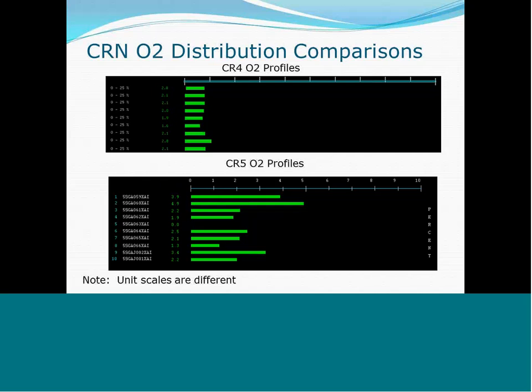So the only thing different now between 4 and 5 was that Unit 4 got what they called the CCM, the Continuous Combustion Management System. Now this is the O2 grid on Unit 4 compared to Unit 5. We can see a much flatter O2 profile, and obviously I'm sure you note a lower O2. Because they're measuring CO, they know that since they turned the CCM on, the CO was removed. Now they're able to back off their O2. And by backing off their O2, they're improving plant efficiency and they're reducing thermal NOx.